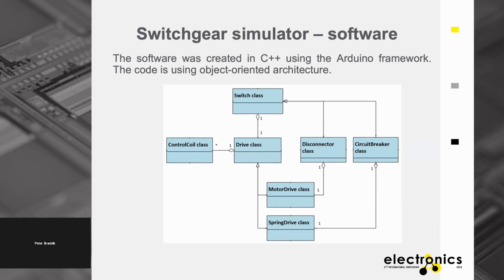The reason for this separation is that circuit breakers, if electromechanical, usually use energy stored in the torsion of an iron bar or spring, and the reaction is very fast. This is because if there is a short circuit and the circuit breaker must switch off the faulted currents, the opening must be very fast. So there is no place for a conventional motor; it must be done by energy stored in the torsion of a spring or metal bar. The activation time is very quick and fast, and the switching on and off action is also very fast. On the other hand, there is limited energy that can be stored by this torsion.